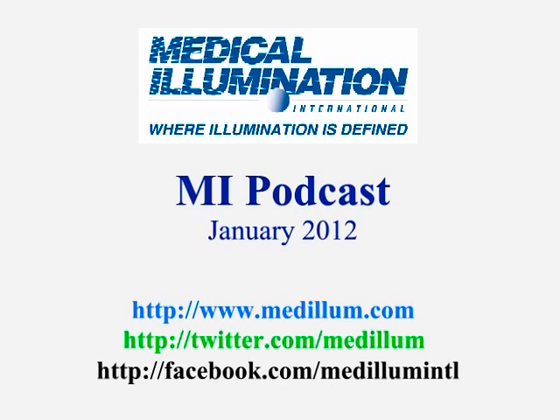Okay. And obviously one other factor would be, let's say that this was an operating room or part of an OBGYN unit or what have you, where they have 30-year-old lights that maybe were not as structurally challenging at the time that the hospital was constructed. Now they're bringing in, let's say, our System 2 series, which is a totally different animal. Then there you might be crossing over into the realm where just an electrician might not do it. You also might have to bring in a contractor and a structural engineer.